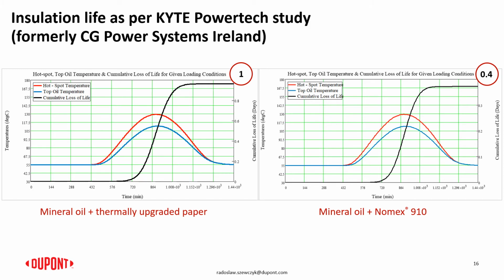When this design analysis was done and the insulation life, or the loss of life, was calculated during such a typical loading period, it was observed that the application of the alternative insulation system, in this case Nomex 910, so the thermally upgraded paper enhanced with Aramid, quite an economical solution for the paper, when combined with mineral oil, already offered a significant reduction of the insulation degradation with the same temperature, so with the same design, just different materials used for the winding insulation.